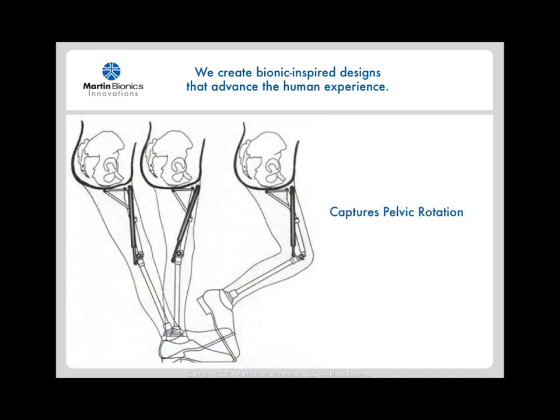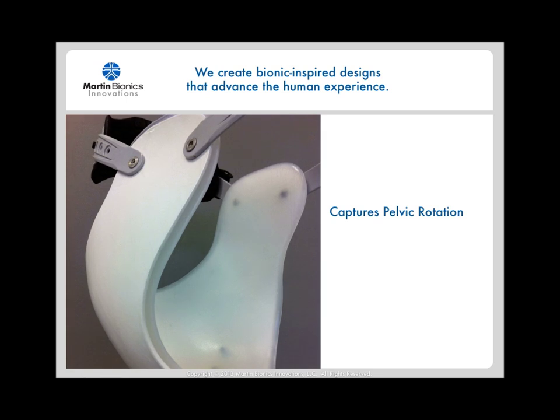To control a hip-level prosthetic limb, the user tilts their pelvis forward, which initiates the hip and knee movement into the swing phase of gait. However, the old bucket-style hip sockets are comparatively loose from the front to back and limit the amount of pelvic rotation that can be captured to control the prosthetic limb. The anterior and posterior wings of the Compliant Force Distribution interface are specifically designed to capture nearly all of the pelvic rotation and make control of the prosthetic much easier.